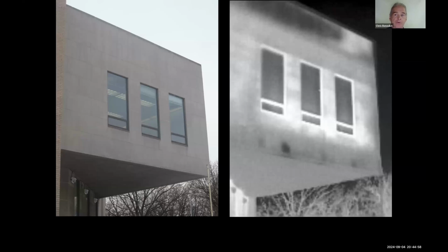The top of the wall is cold because it's a parapet, a wall around the edge of a roof. It's probably 36 or 42 inches high. So the top 4 feet or so of the wall is cold because there's no building behind it heating it. It's unheated on both sides. It's exposed to outdoor air on both sides. So it's black, it's cold.